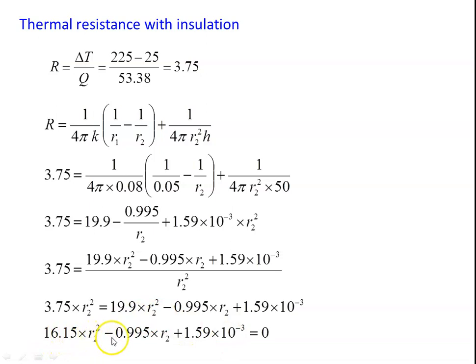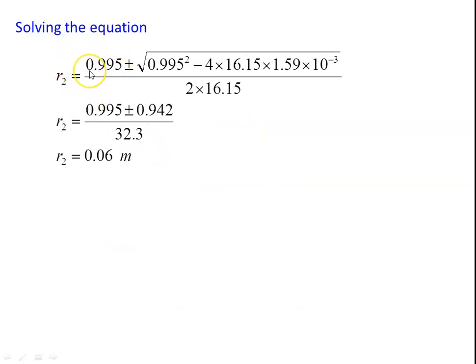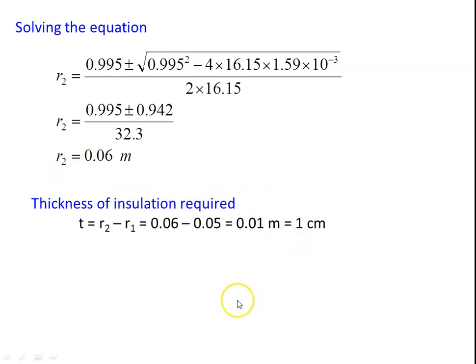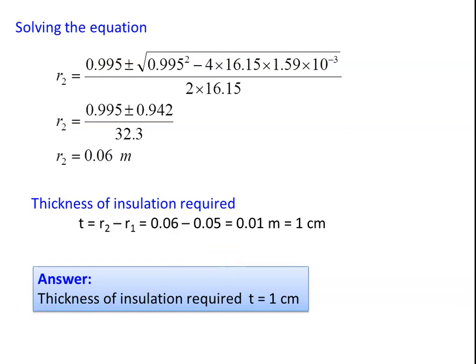The quadratic equation is: 16.15r₂² − 0.995r₂ + 1.59×10⁻³ = 0. Solving using the quadratic formula: r₂ = [0.995 ± √(0.995² − 4×16.15×1.59×10⁻³)] / (2×16.15) = [0.995 ± 0.942] / 32.3. This gives r₂ = 0.06 m. Therefore, the thickness of insulation required: t = r₂ − r₁ = 0.06 − 0.05 = 0.01 m = 1 cm.